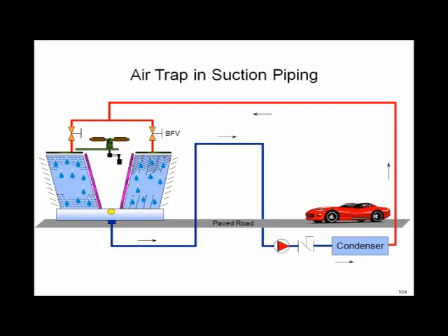What are we going to do about it? Obviously, bad design. Obviously, better off to take that piece of piping, put it underneath the road, and make it go. But they wanted to make it work that day. They wanted it to work that day for some period of time. What would you do? How would you get it going? This is what we did. We got a pipe fitter, a good friend of ours, to go stand in the base of that cooling tower with a piece of plywood. So it's a bottom outlet tower to the left. We cut a piece of plywood and put it over the bottom outlet of the tower, and got a guy to stand on that piece of plywood to try to keep the water from going out the overflow that we're putting in there. We went to the top of this air trap and put a big air vent.